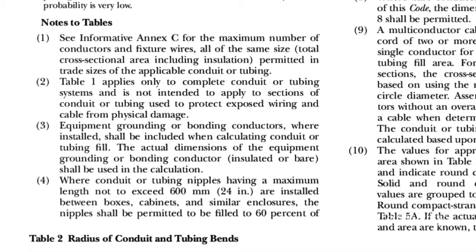So that answers our question: yes, we do need to include the equipment grounding conductor. And so that gives us a total of eight 14-gauge conductors and two 12-gauge conductors.